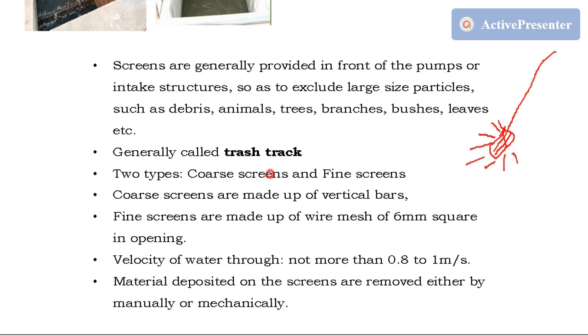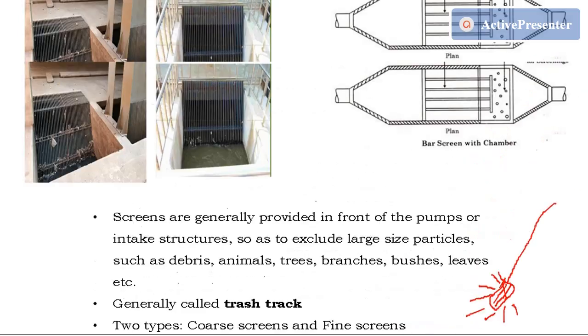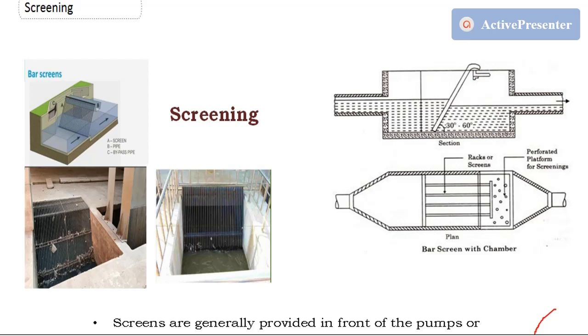There are two types of screens: coarse screens and fine screens. Coarse screens remove coarser material and fine screens remove finer material. Coarse screens are made up of vertical bars as shown, and fine screens are made of wire mesh with usually 6 mm square openings. The velocity of flow should not be more than 0.8 meters per second when water is approaching the screen. Material deposited on the screen is removed either manually or mechanically — the screens are rotated continuously so that deposited material can be removed.